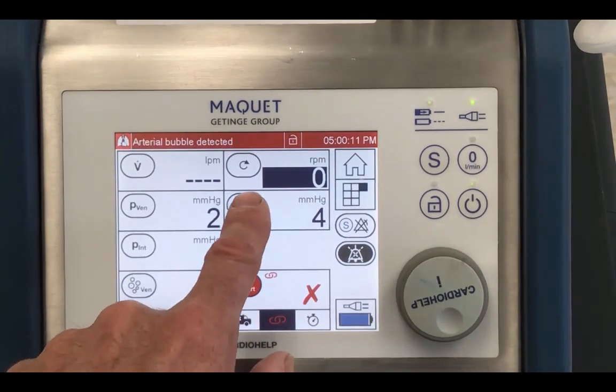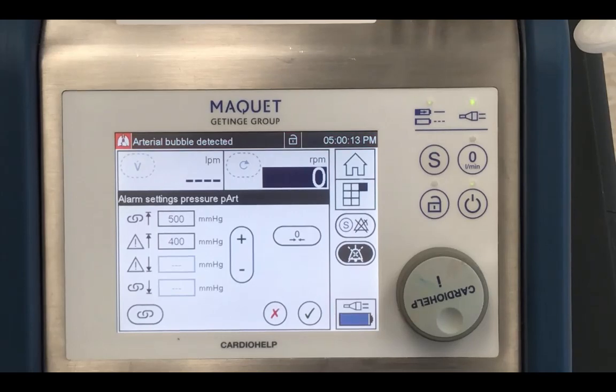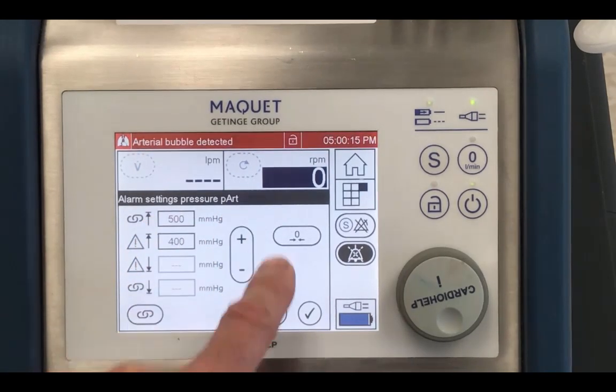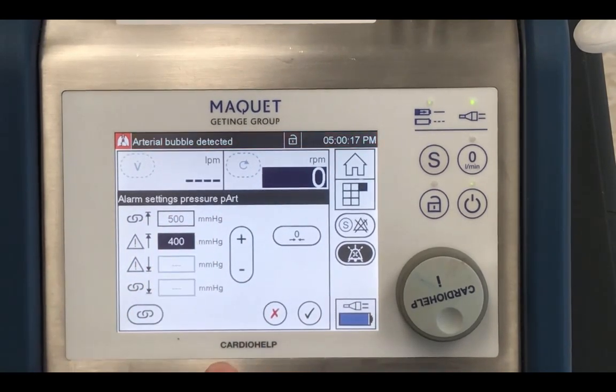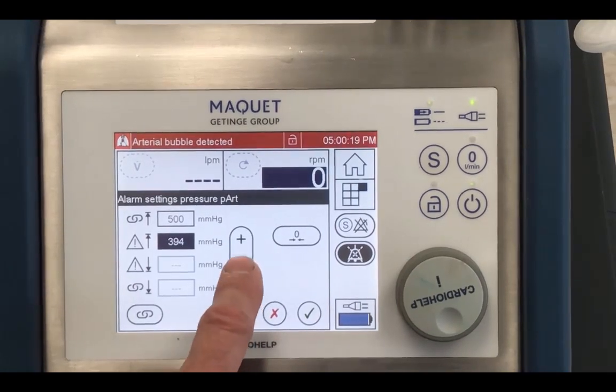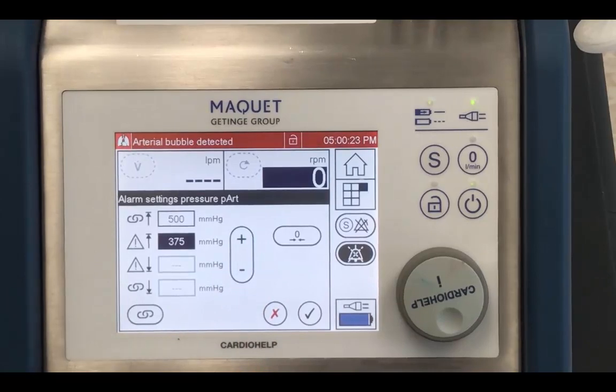So that's how you set interventions. You can set the interventions and the limits for pressure arterial. Let's select the 400, turn that down to 350, just for an example, or 375. Now it's down to 375, and if we go up here and hit the 500, the 375 is ready to go. It'll enter if I hit the green checkbox.